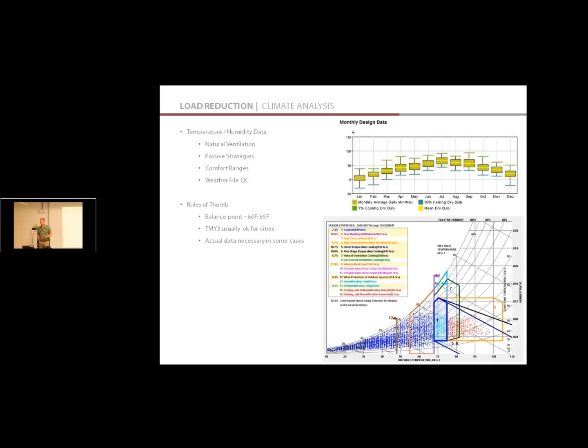Typically I figure a balance point for a building—the outside air temperature when it switches from heating to cooling. A typical office building is probably around 60 to 65 degrees. There's a lot of fluctuation depending on building type, but that's a good rule of thumb early in a project.